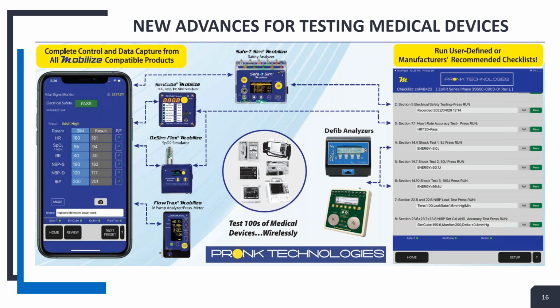It's now going to put the defib analyzer into pace mode, and after it samples some pulses, you'll see some results come through as well. It'll be a string of results, including pulses per minute and the current. So what kind of results did you get? Current is 29.8. Width is 40.02, and rate is 39.9. Yeah, good. So that's a pass. Of course, you hit pass and then you hit done.